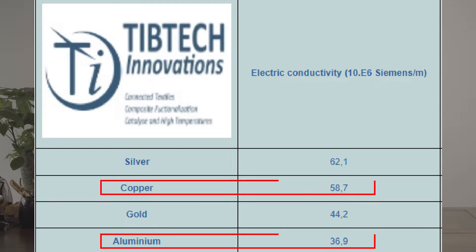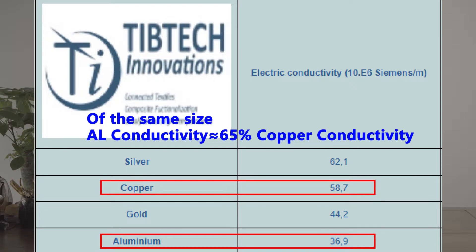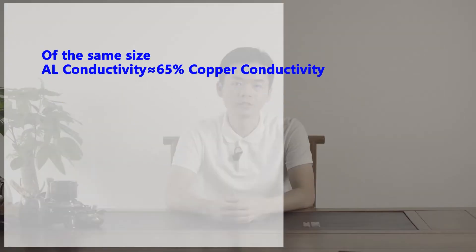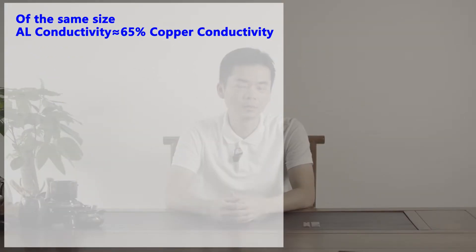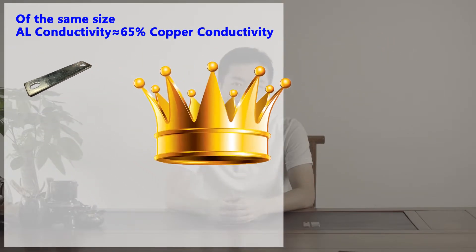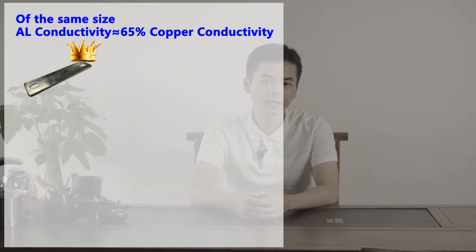Conductivity is the most frequently mentioned point many people use to argue that copper busbar is superior to aluminum busbar. Well, this statement is only half of the truth. On one hand, for the same size of the two kinds of material, aluminum busbar conductivity is only 65% of copper busbar. So in this sense, copper busbar totally outperforms aluminum busbar.